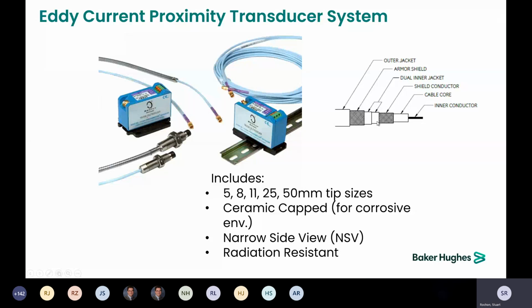The 3300 had a center core, the insulator, a shield, which was the negative, and then just an outer jacket. The 3300 XL increases that protection to having a dual jacket, another metal mesh shield, and then an outer jacket. This helps with abrasion resistance and RF. So the 3300 XLs are much less susceptible to noise and damage. All right, we're going to stop there for any questions on proximity systems.